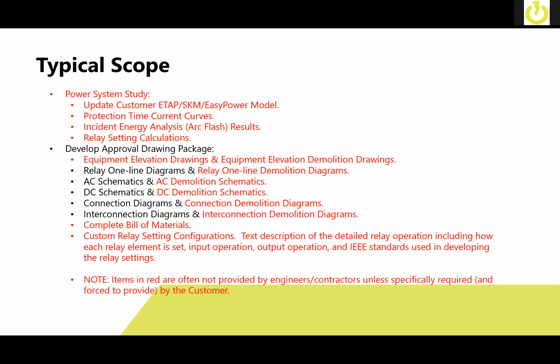And we also want to provide a full service where a lot of times you may call and say you want a protection retrofit. Well, if you're maintaining a power system model in ETAP, SKM, Easy Power, for instance, a lot of times what gets retrofitted does impact your arc flash. So one of the things that we typically do is we update your power system model. We update your protection time current curves, reperform the incident energy analysis or arc flash, and give you the results. And then we use that to base the relay settings calculations on to make sure that it meets your needs.